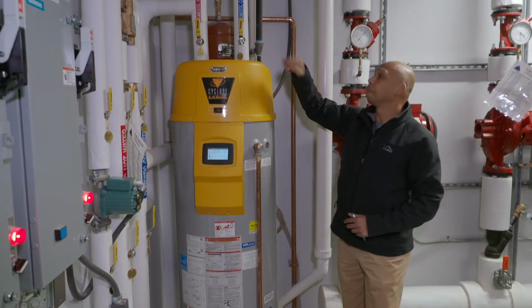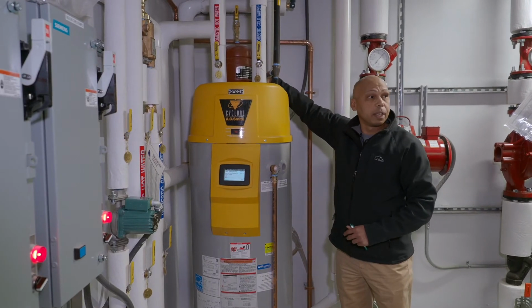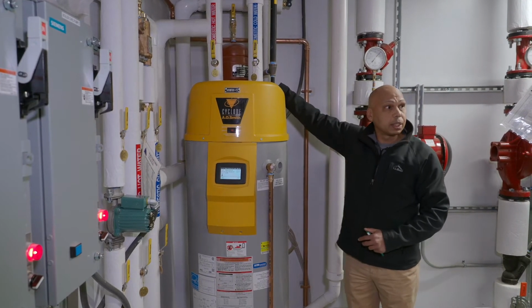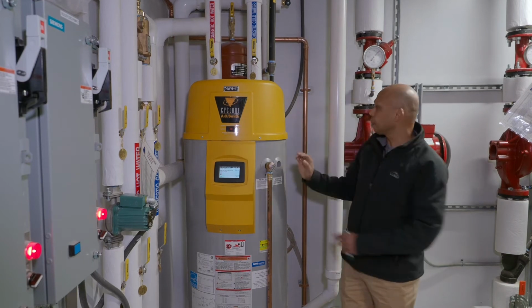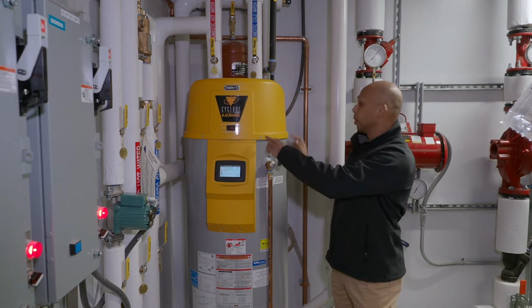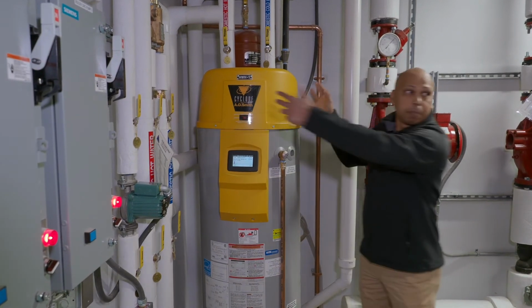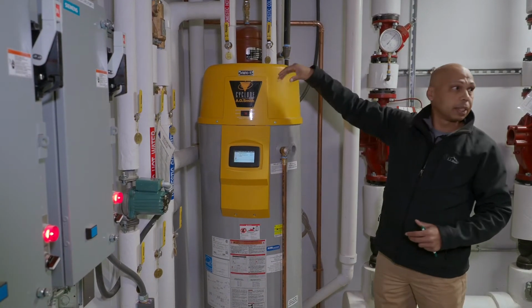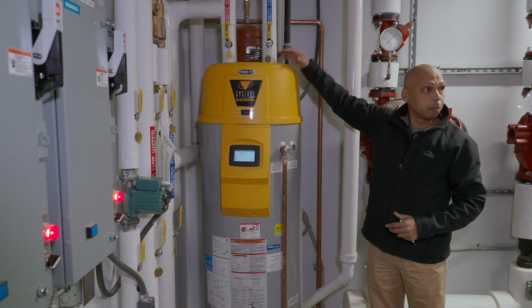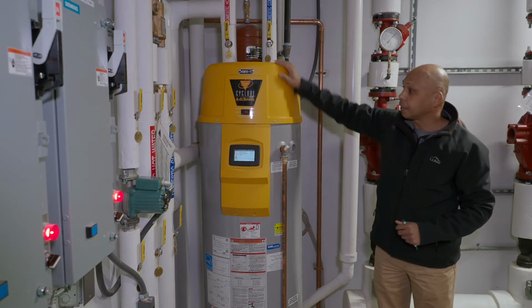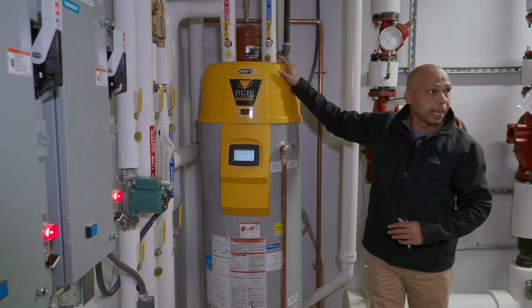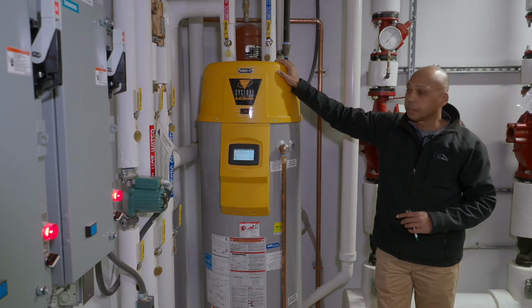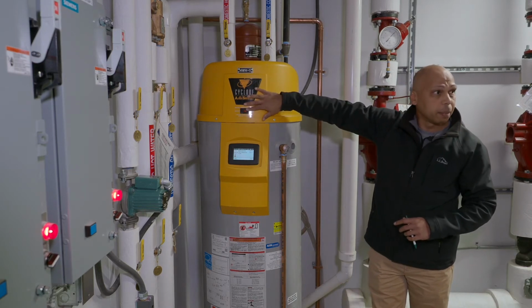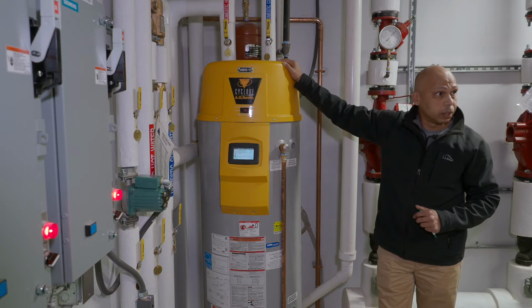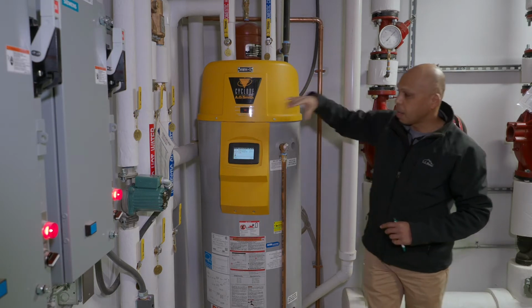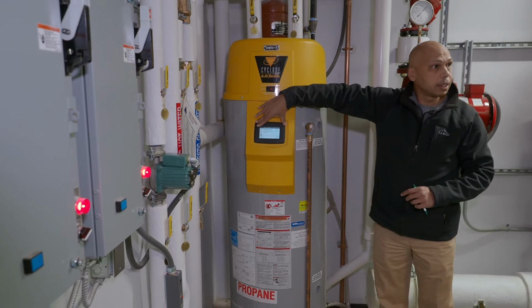Behind here, including the burner and the blower, you'll have a couple of pressure switches. The gas valve is back here. You have to get through here to see all the controls. You pop off these couple of screws, pull this shroud off, and then you'll be able to see the burner, the gas valve, your pressure switches, your control board, etc. Before you do any maintenance work, replacing any controls, make sure your unit is disabled, and also shut off power to the unit.